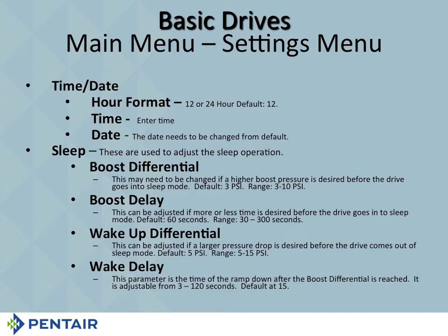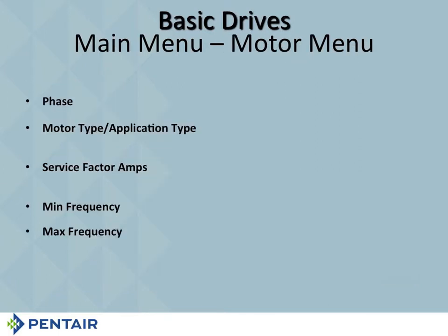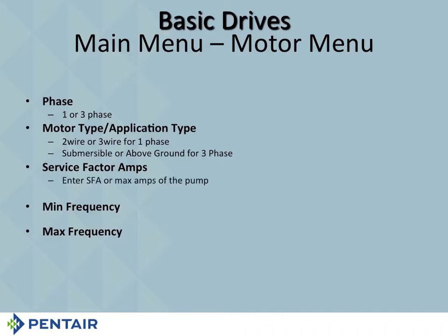It's up to you. Under motor menu, it's going to ask for the phase. And then, of course, remember, which are you picking? And that's going to be based on the phase that you pick. It's going to ask for service factor amps. All right. Remember, your minimum frequency is going to be 30. It can be adjusted up if need be. It cannot be adjusted down.